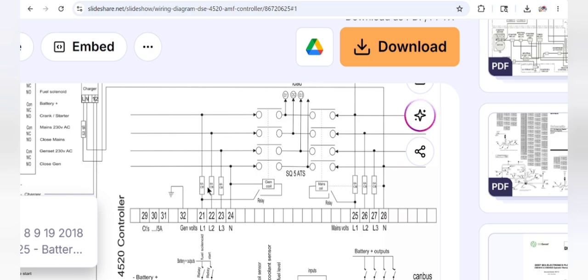As you can see, we can also use our circuit breaker, CB. And here, as you can see, the relay coil, the contactor coil A1 A2, we will feed 1 phase and 1 neutral from the generator supply. Okay, and on the other side, as you can see, this is the gen coil, and this is the main coil contactor relay.